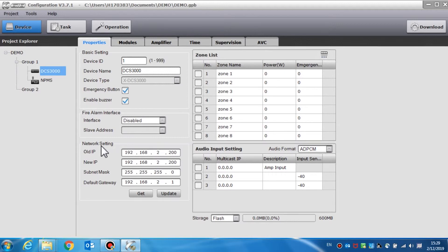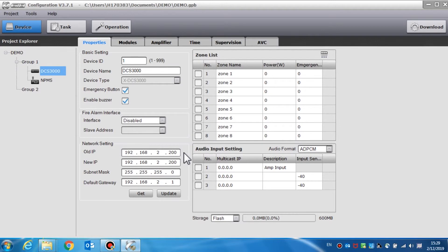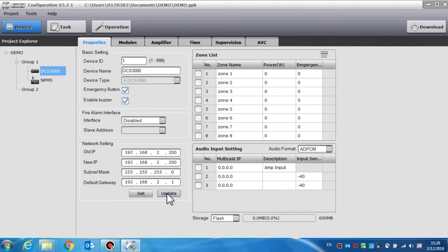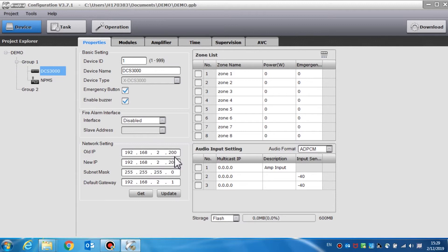The network setting is used to set the DCS network parameter. For updating the network parameters of the system devices, it should be connected to a computer whose IP address is set to the same IP address as the DCS. Click the update button for setting the IP address of the DCS. The two IP addresses will be the same. The default IP address is 192.168.2.200. If you do not know the IP address of a certain DCS, you can find it on the front panel of the DCS. Press all and monitor buttons in order and release them in reverse. The DCS will recognize the present IP address.